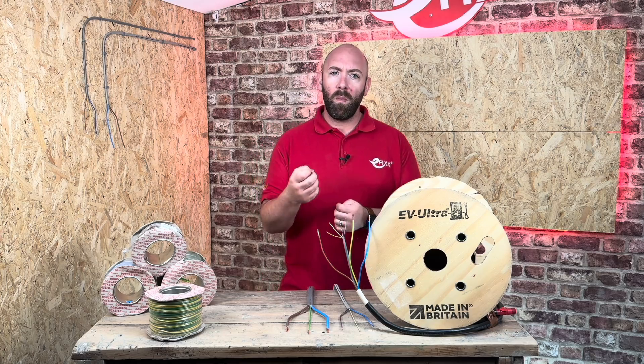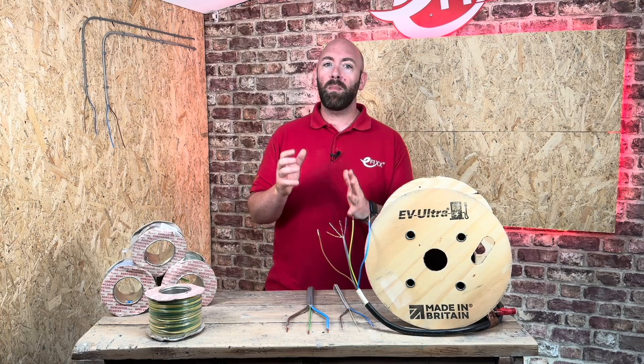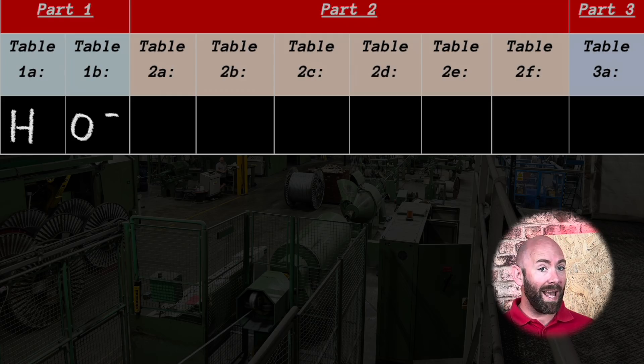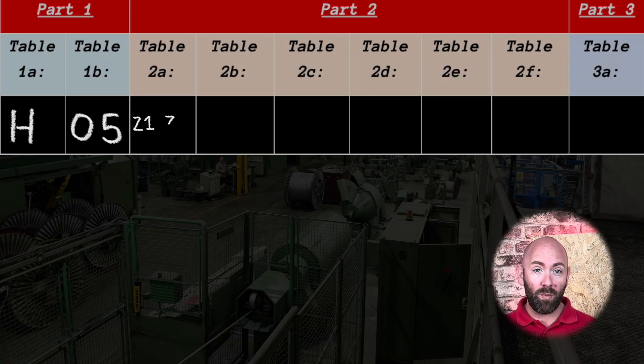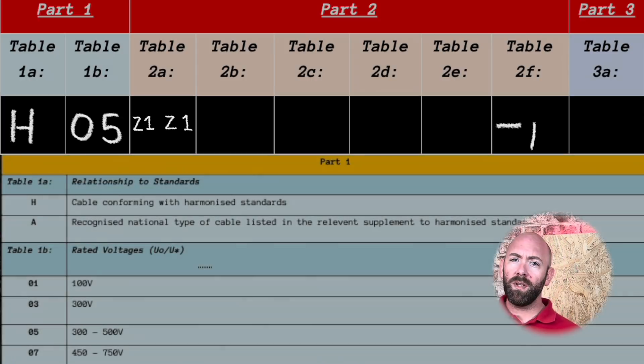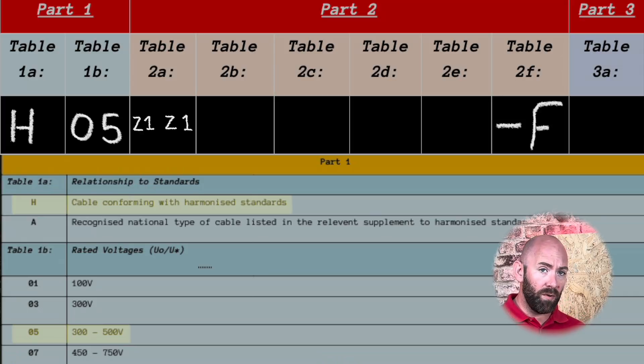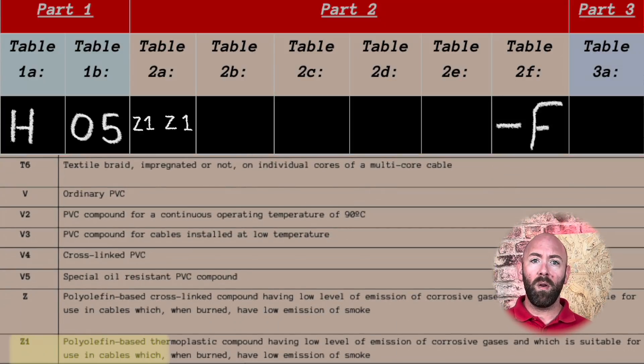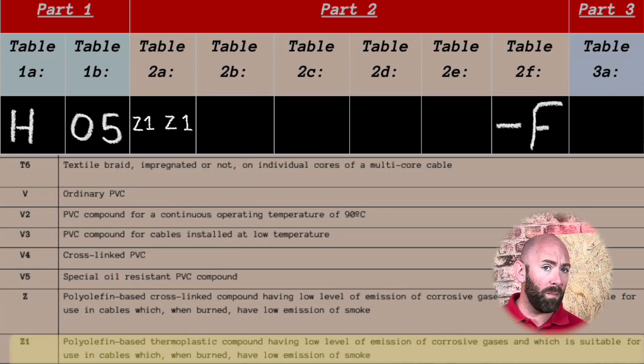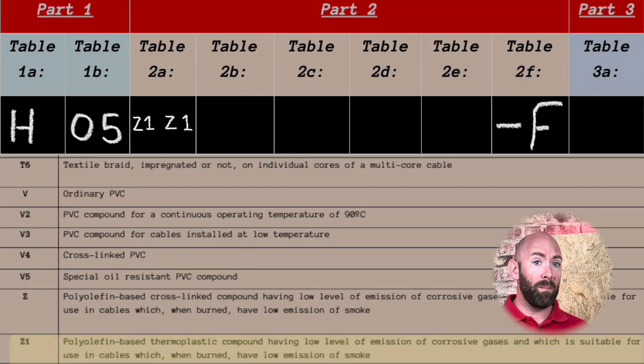Let's look at one more cable code that has grown in popularity due to its unique properties. The code is H05Z1Z1F. We know it's a harmonized cable with a voltage range of 300 to 500 volts. The inner and outer insulation is made up of a polyolefin-based thermoplastic compound which has low levels of emissions of corrosive gas and has low emissions of smoke when burnt.